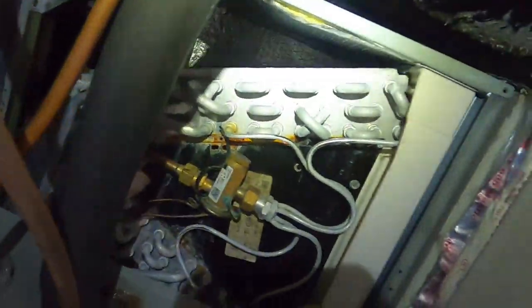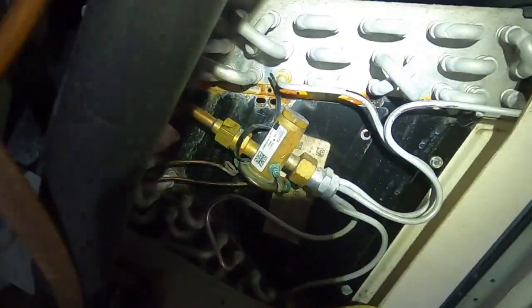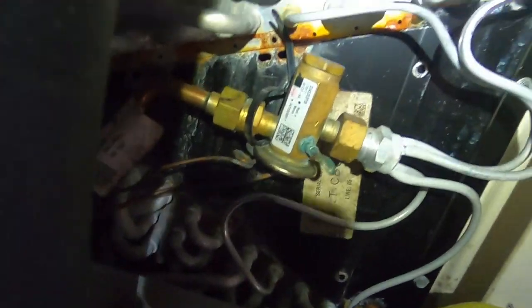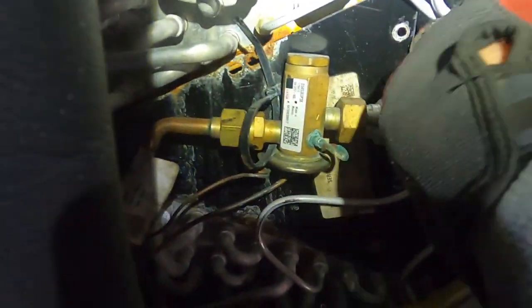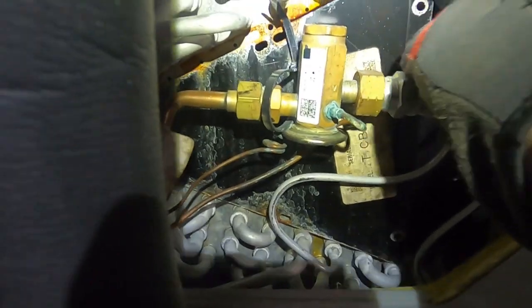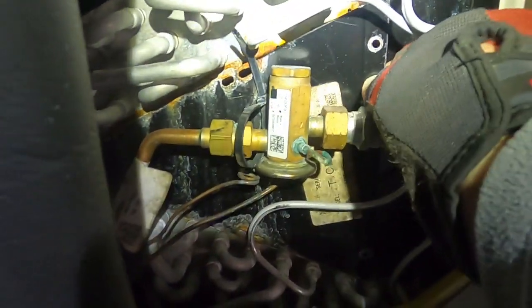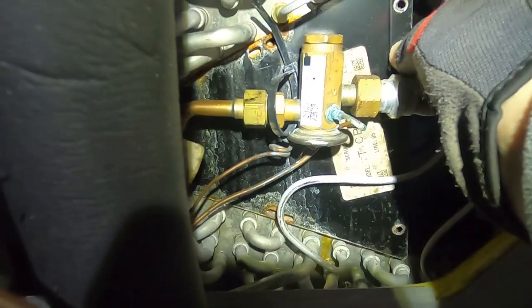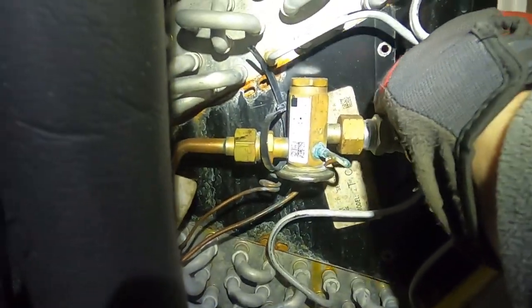So first thing I'm going to do is go in through the evaporator coil. You've got to pull that out, which I already know nobody else has ever done, so I don't know how the other company found this alleged crack in the heat exchanger. I mean, there may be one, but if you see, this panel is still zip tied right there to the TXV, so I know that no one's ever pulled this out to look back there.